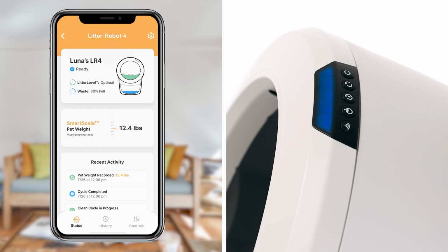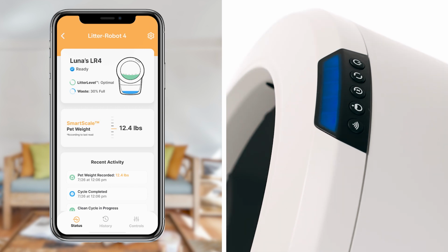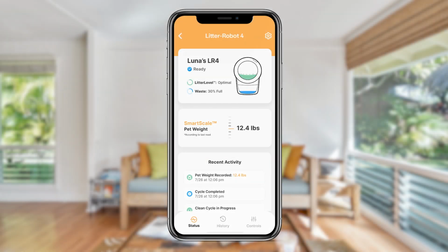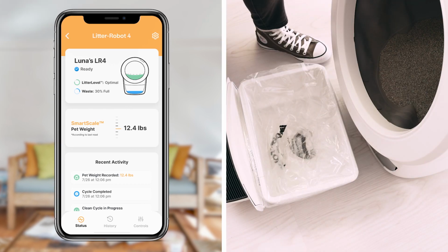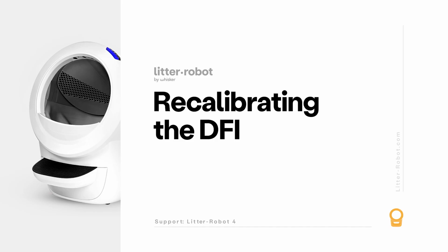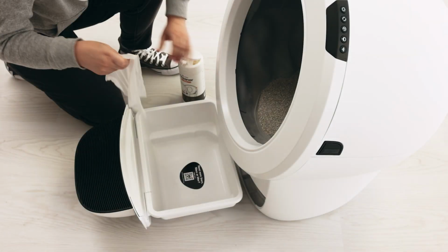Before you check the waste drawer level on the app to ensure it's accurately representing the level in the waste drawer, press the Reset button, then press the Cycle button to start a clean cycle. Check your app to ensure that the waste drawer level displayed is accurate. If the waste drawer level in the app is still not accurate, we'll need to further inspect your unit for next steps. Occasionally, the Drawer Full Indicator, or DFI sensor, will require a recalibration to ensure proper measurement accuracy.